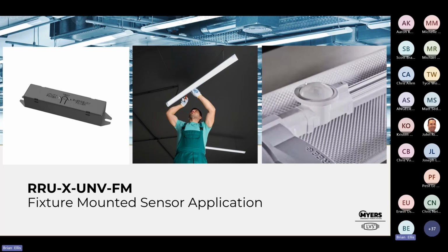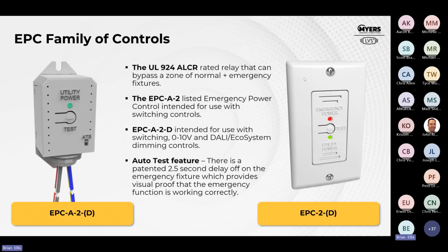By its very nature, if the control device is in the fixture and that fixture is emergency, then the only fixtures in the lighting control zone are emergency fixtures, which makes it a perfect application for a shunt relay. But most of our applications are going to fall under this UL 924 ALCR listing, so automatic load control relay. So what's different about this?